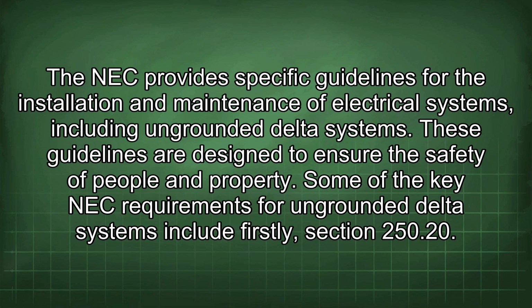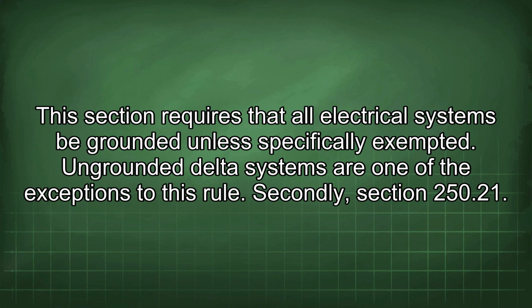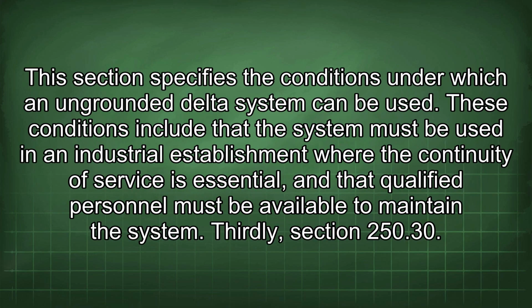Some of the key NEC requirements for ungrounded delta systems include, firstly, Section 250.20. This section requires that all electrical systems be grounded unless specifically exempted. Ungrounded delta systems are one of the exceptions to this rule. Secondly, Section 250.21. This section specifies the conditions under which an ungrounded delta system can be used. These conditions include that the system must be used in an industrial establishment where the continuity of service is essential, and that qualified personnel must be available to maintain the system.